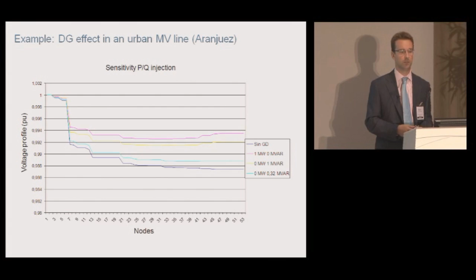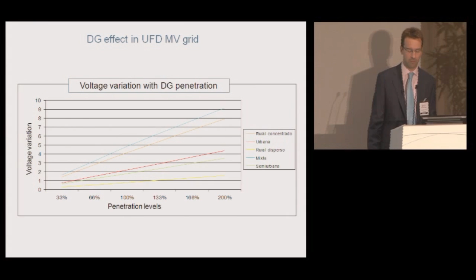And as a summary, here you have the whole picture for the different classifications of our lines, for rural, urban, semi-urban, etc., and for different penetration levels. What we're seeing today is that we have no more than 60% of distributed generation connected in our lines. So the variation in our lines, taking into account the different classifications, is up to 3%, which is quite controlled, which is all right. But the problem is, if we have higher penetration levels, be careful, because the margin is going up. The voltage variation is much more significant.